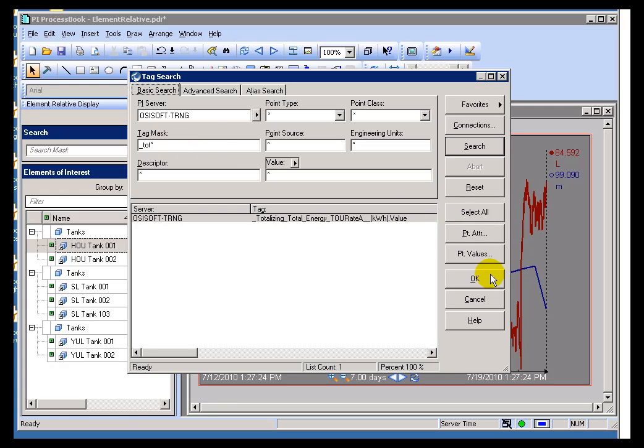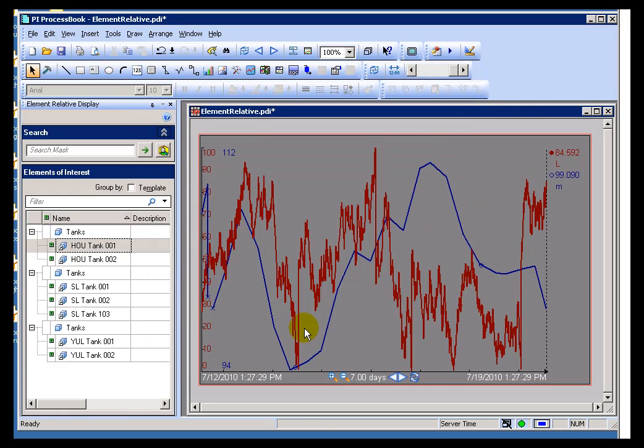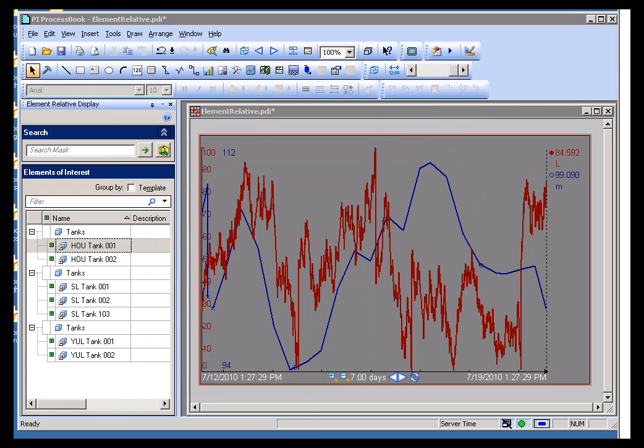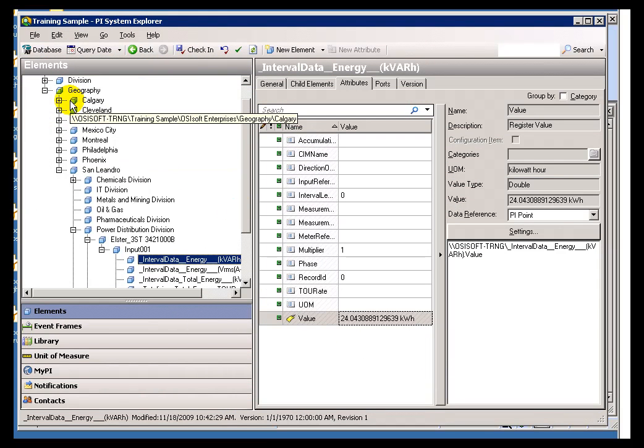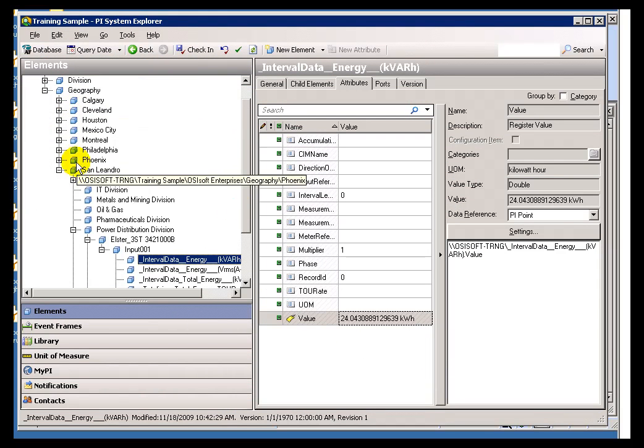Unfortunately, that fourth Tag doesn't fit the Naming Convention. It was created a few months later, and it was a Totalization. So for me to find that particular Tag, I would have to know that it begins with the letters Underscore TOT, and then I would find that particular Process Value. Because we find there are so many customers that would have these large systems and they would like a better mechanism for navigating, what we've created is more of a hierarchical view of looking at your PI data.